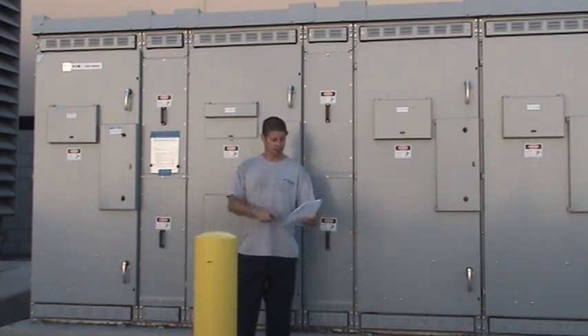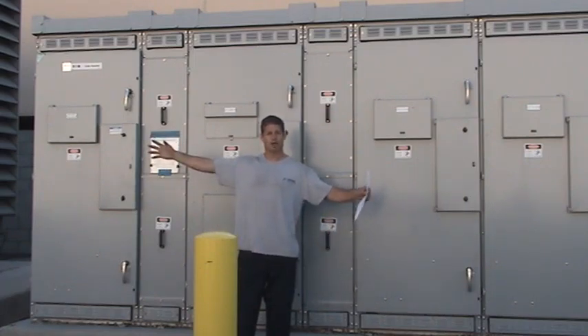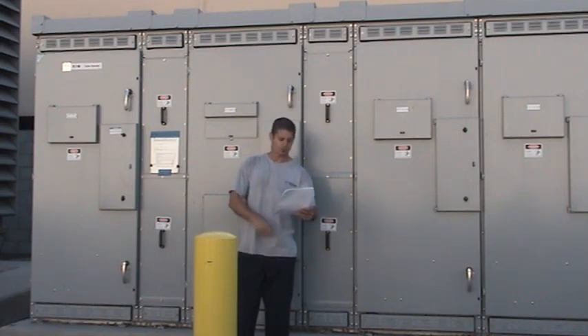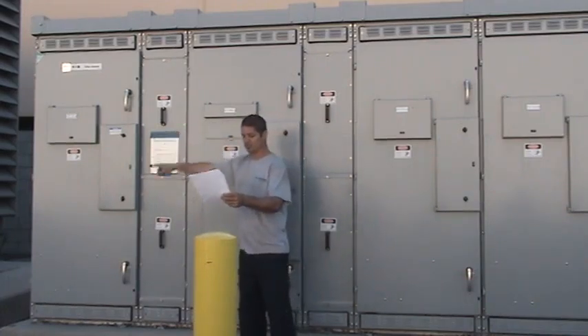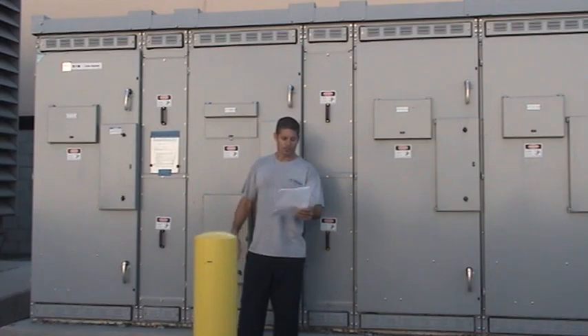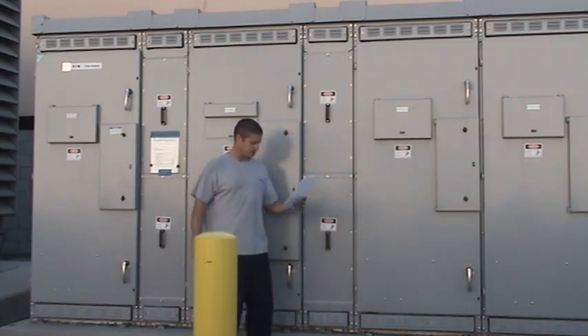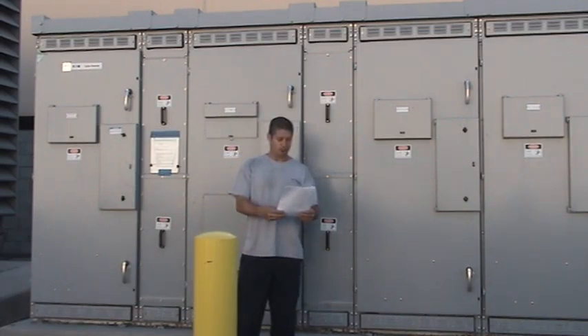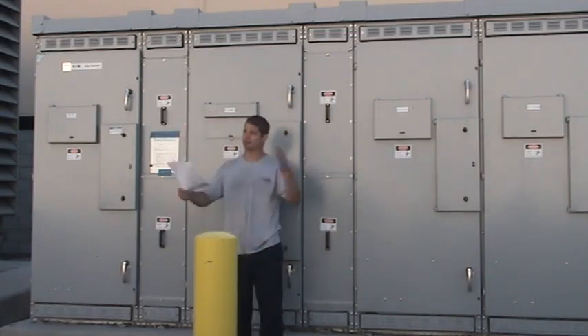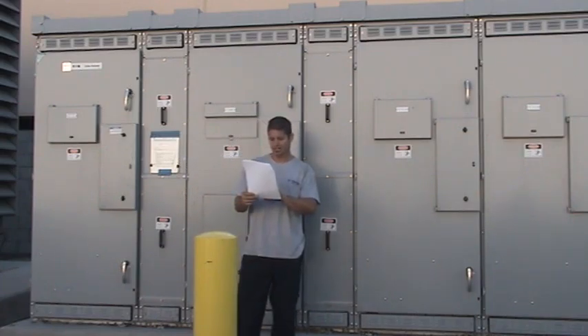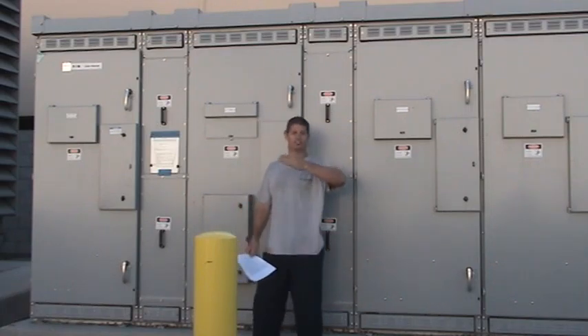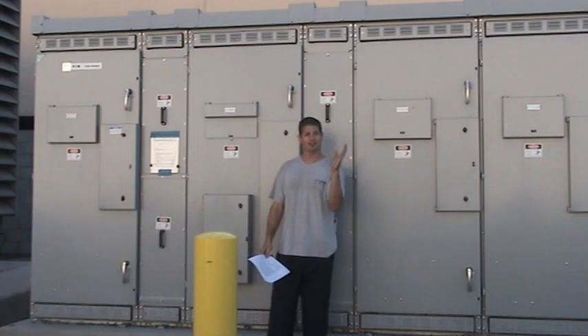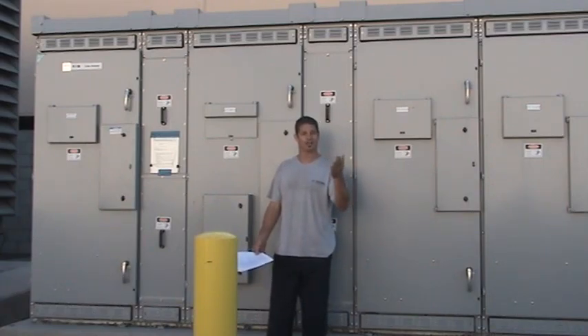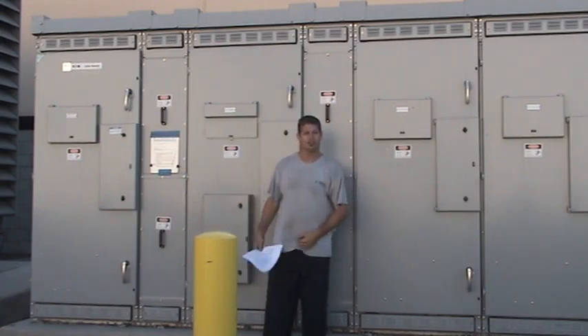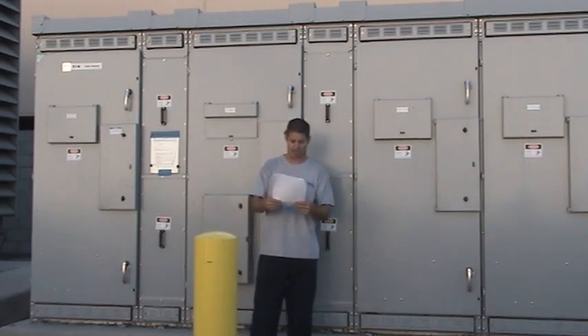Second would be total loss, and that's what it explains down here further on the last section over here. You lose both, right? You have a 60-second delay from the loss of voltage. This gear sends a start signal to the generator. The generator then sends a ready to accept load signal back to MSV14, which is right here. Then the main switches will open. So the main here and the main there will open, on both sides. It confirms that the switch is open, so it even sends a signal, hey, we're open now. It's a separate signal to make sure that it's open, right? Because we don't want to parallel power feeds into each other, or cross power into each other. It'd be bad with medium voltage.